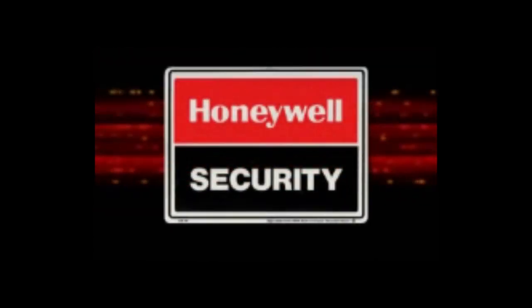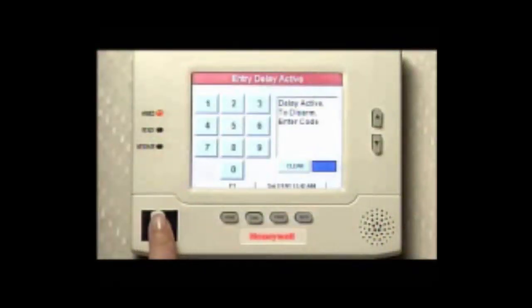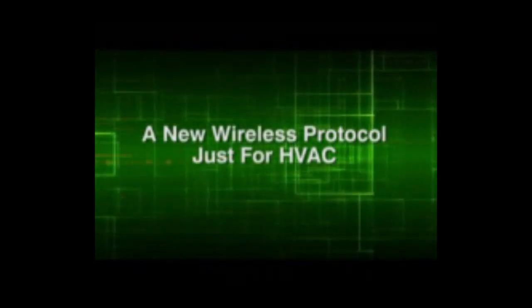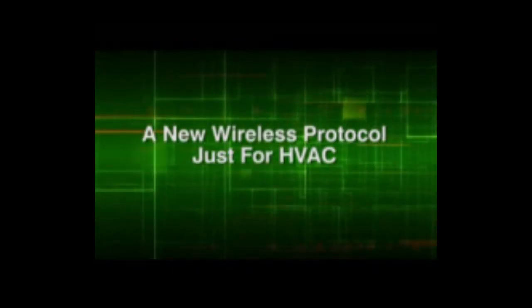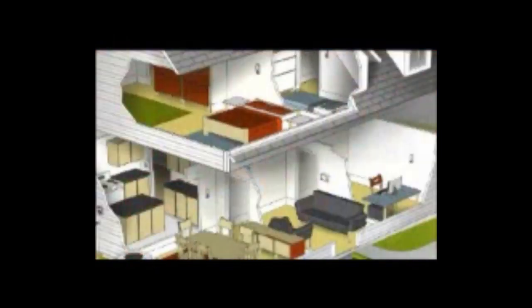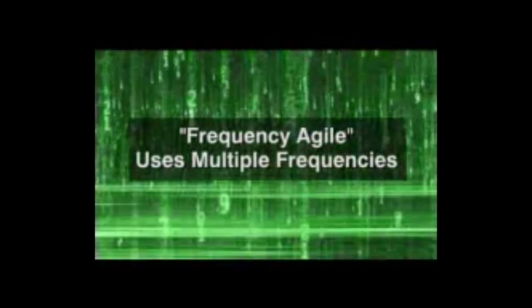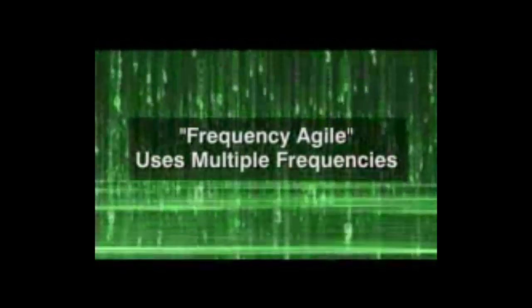The first thing we had to do is figure out what customers really want. We started with Honeywell Security, which has put millions of devices in homes, very reliable, done it for many years. We got all the groups together and said, we need a new protocol for HVAC and residential - what should we do? We need the same level of reliability as security. In the HVAC industry we've seen no protocols like this; if there were an industry standard we would have used it if it met what our customers needed. But in a house you've got different materials - metal, stucco, brick. What we did in the end is build a system with multiple frequencies, called Frequency Agile - instead of staying on one frequency, it moves across 50 different frequencies. When we do that, the FCC allows us to transmit at a higher power.